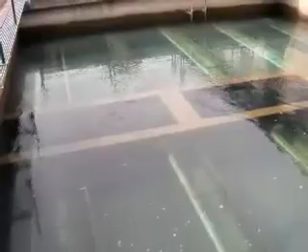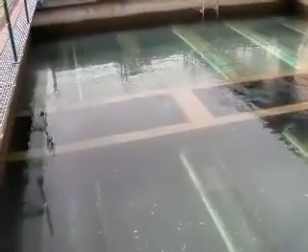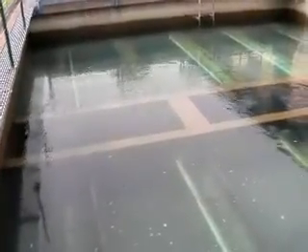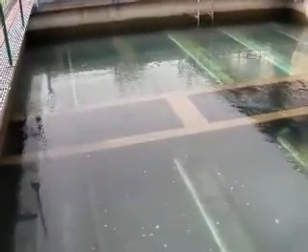With that and the chemical adjustments, we were using our filter aid poly more efficiently. Like in the winter, we add a little bit more poly to catch the particles on the top of the filter better, and we were able to get more time out of them. On average we were getting about 40 hours on the filters, and we were getting 70 to 80 hours. So there's the numbers. And we averaged it all the way through the whole winter. Even during the high turbidity, we were running 15, 20, sometimes spikes of 150 NTUs and it was handling just fine.